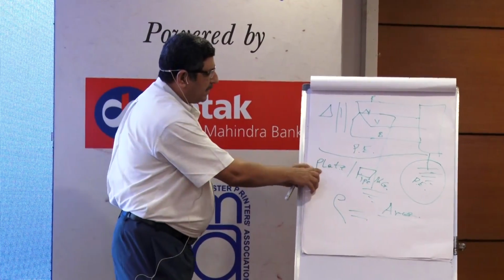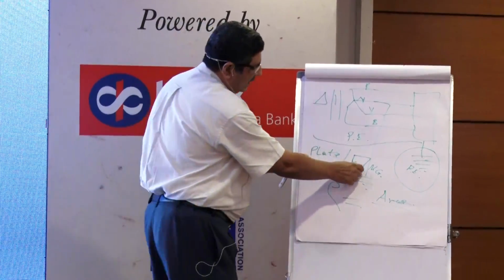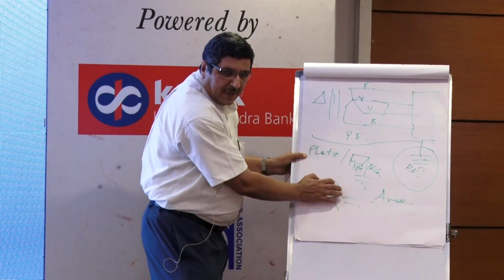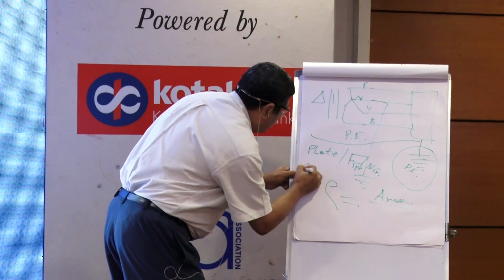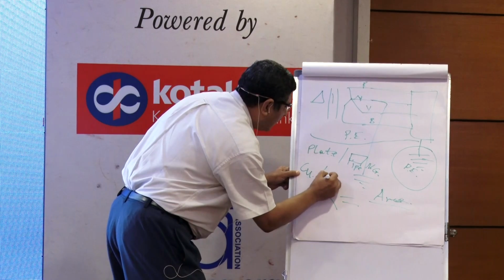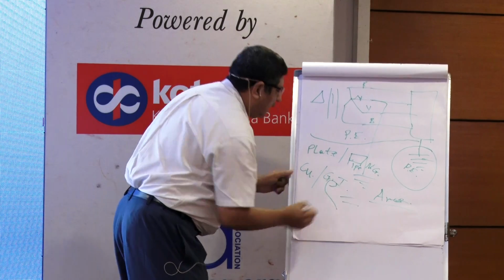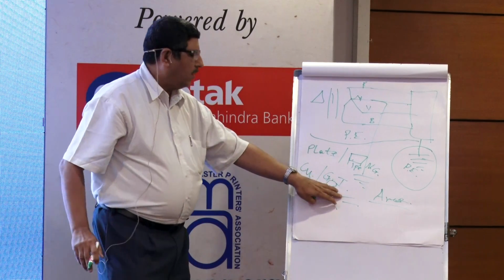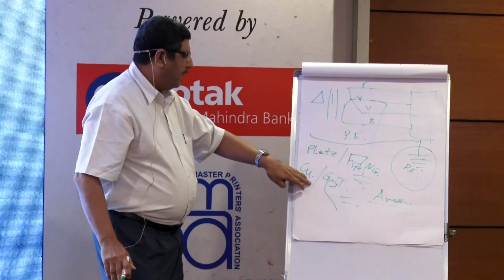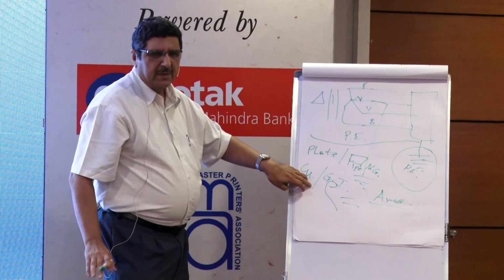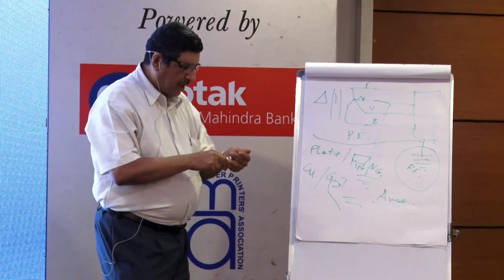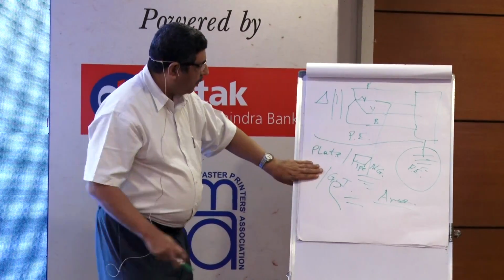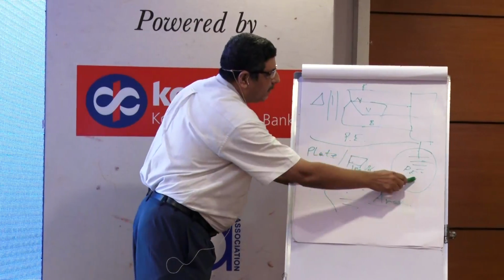Now instead of a 3 mm thick plate, I can use a 6 mm or 10 mm thick plate in galvanized iron. So there is one option of copper and second of galvanized iron. A galvanized iron plate will be somewhere around 2,000 rupees, while the copper one will be around 6,000 to 8,000 rupees. So it is 3.5 times or 4 times costlier. I would suggest don't go for copper, go for galvanized for the protective earth.